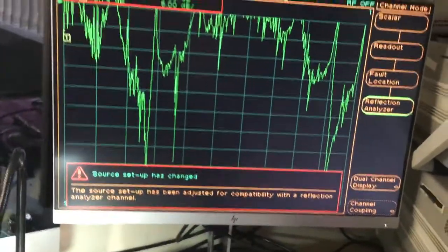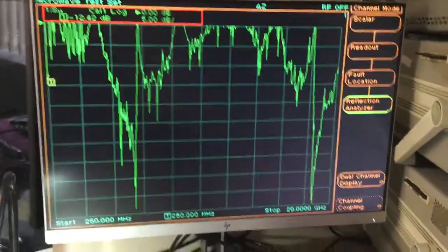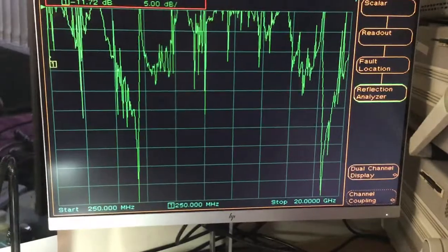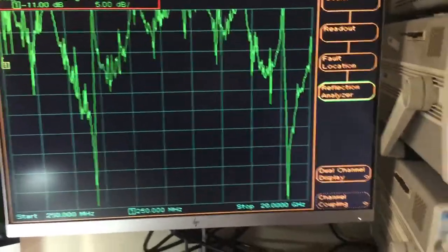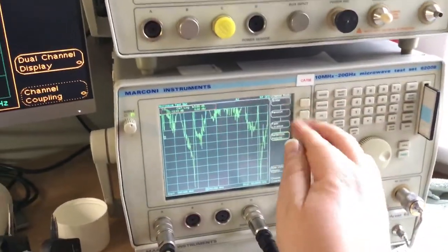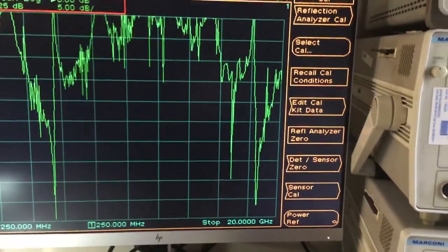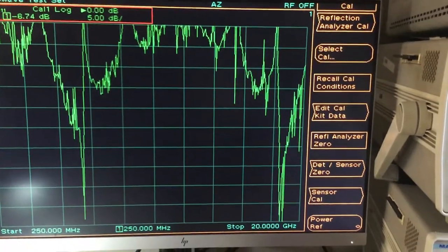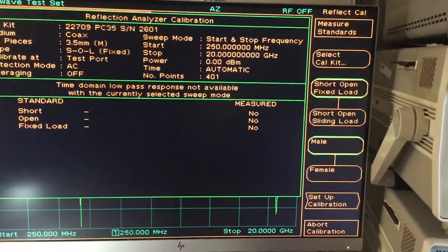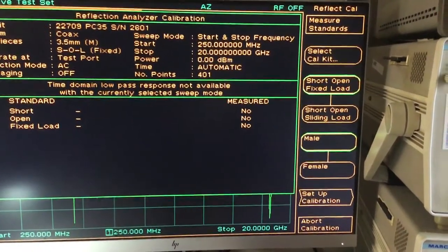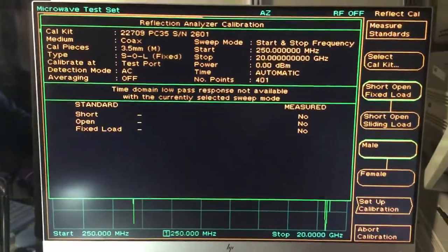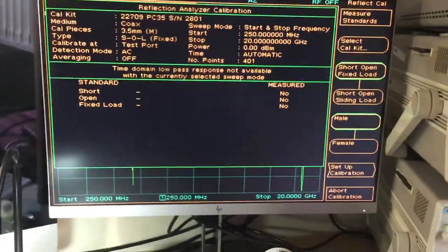We found it. So that reflection analyzer, it's telling us that the source setup has changed as well, and as part of this we'll now need to select calibration on the instrument, and then we can do a reflection analyzer cal, which is up in the top right. We've got different types of cal as well, but we've got a short, open and a fixed load calibration.